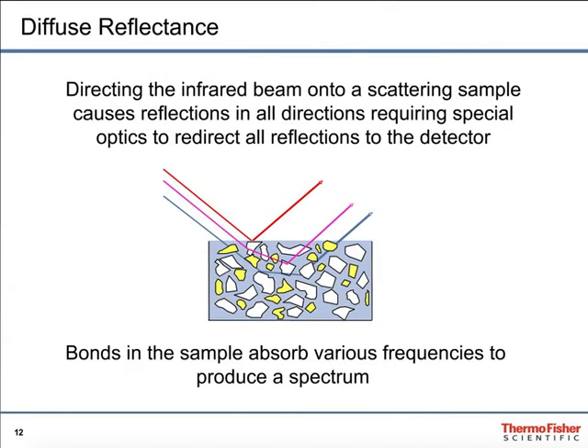The last of the four techniques is diffuse reflectance. In this case, the IR beam is directed down onto a powdered sample or an irregularly surfaced sample. The specular component — the light that's just reflected straight off — is actually ignored by the system. It's looking for the light which is scattered in other directions, where the light has penetrated down into the sample, reflected multiple times, passed through particulates of the sample, interacted and been absorbed, and then reflected out to the detection optics.